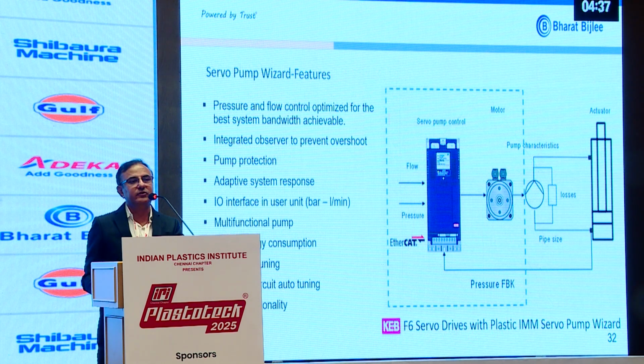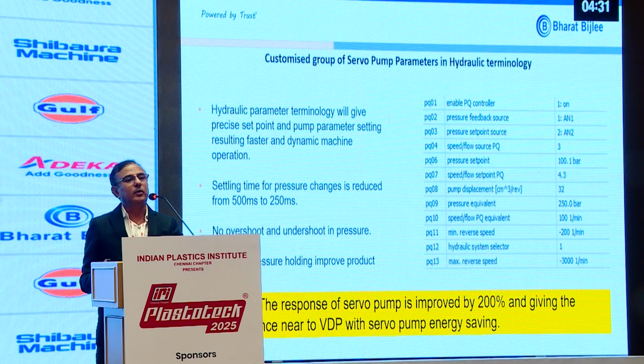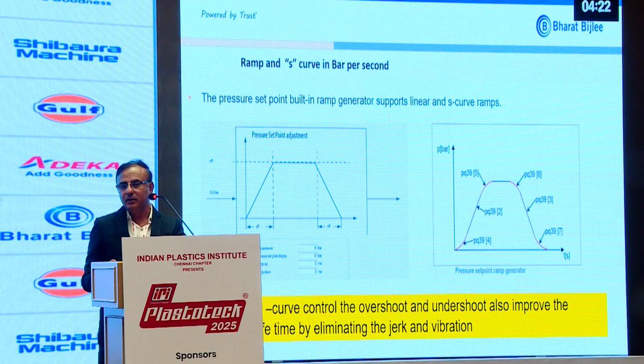It has a Servo Pump Wizard, an intelligent software in the drive for hydraulic technology. The parameters are in hydraulic terminology like percentage flow and percentage pressure, so the operator can easily identify them. It also has an S-curve in bar per second, so you can get fine control of flow and pressure, improving product quality with lower rejections.